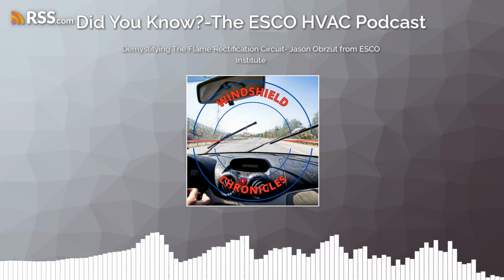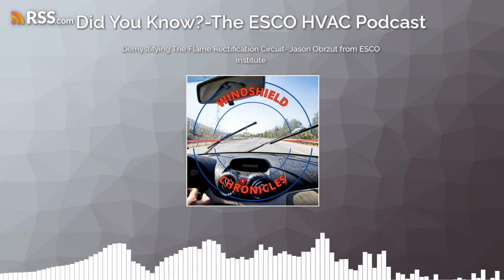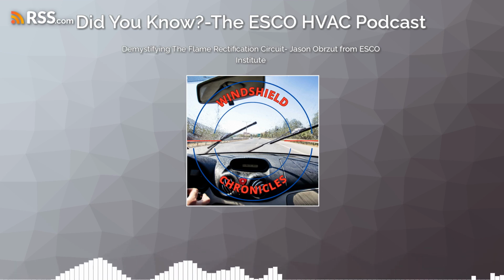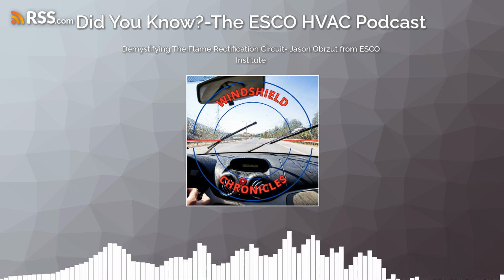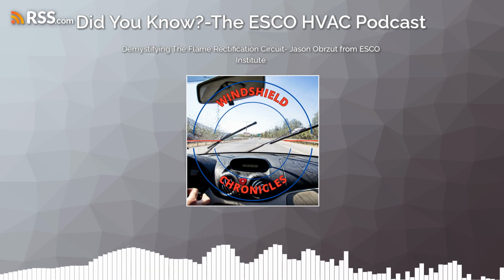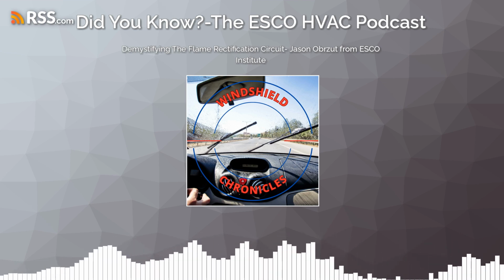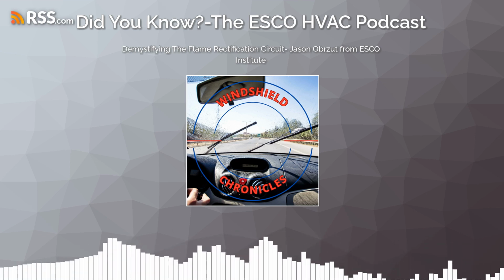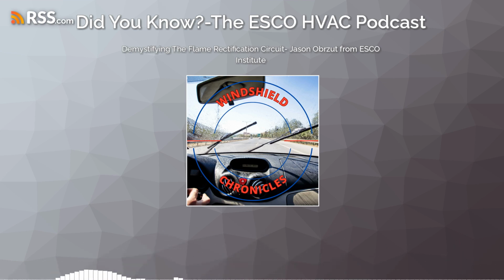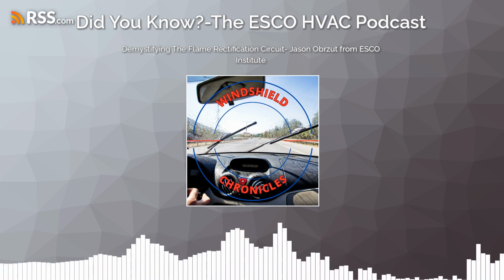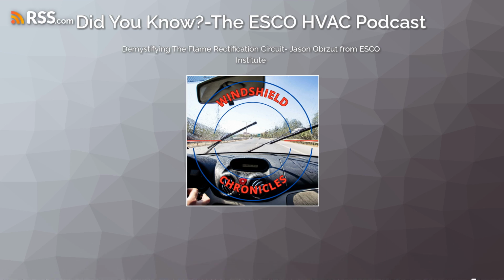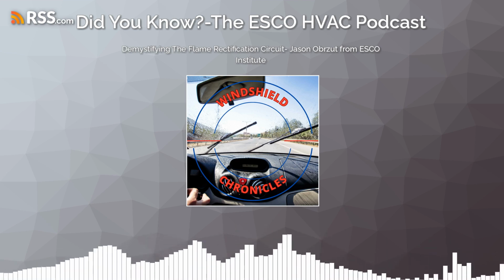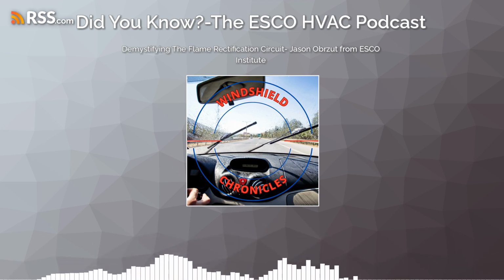So if the pilot went out, the thermocouple or thermopile would stop generating voltage and the valve wouldn't be able to open to let the gas out, because there would be nothing on the other end of that valve to ignite that gas that we were letting out. So it was more like a safety device. And that function, if you will, the safety portion of it, carried over to the flame rectification, but the principles did not. It's a completely different principle.